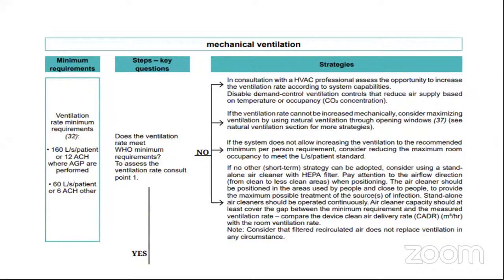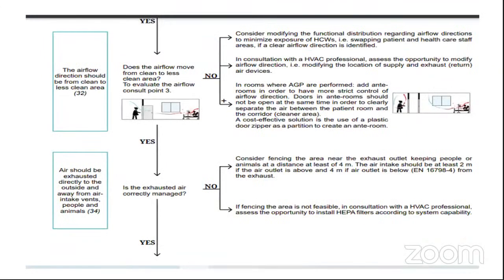The same short-term strategy of using a standalone air cleaner with HEPA filter can also be used in the mechanical ventilation type. If the airflow is not moving from clean to less clean area in a mechanical ventilation system, we can modify the location of supply and exhaust air devices. That can be done by the HVAC professional. And we can make sure that we add an ante-room in order to have better airflow directions.